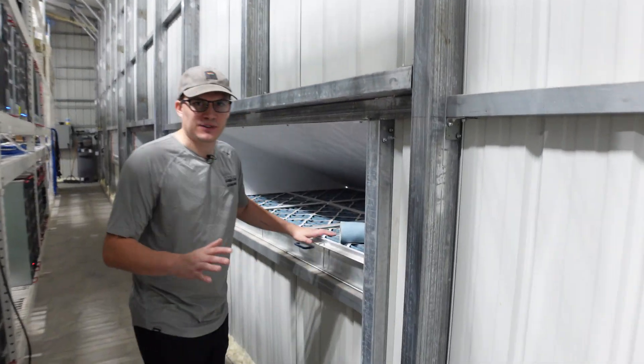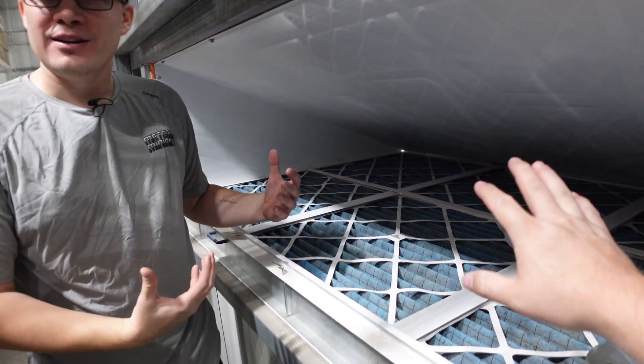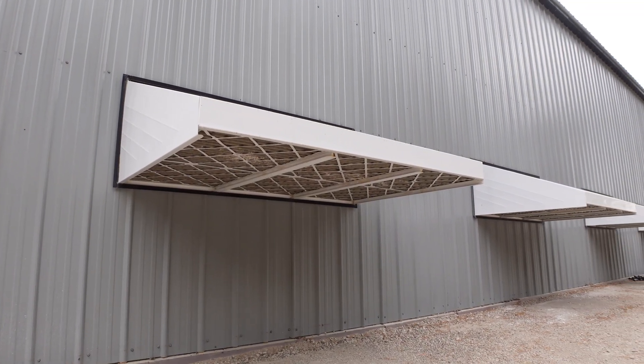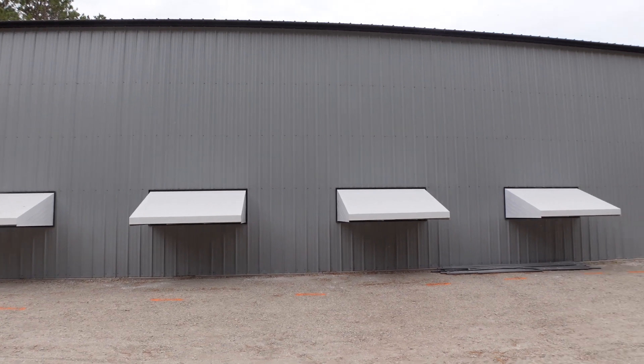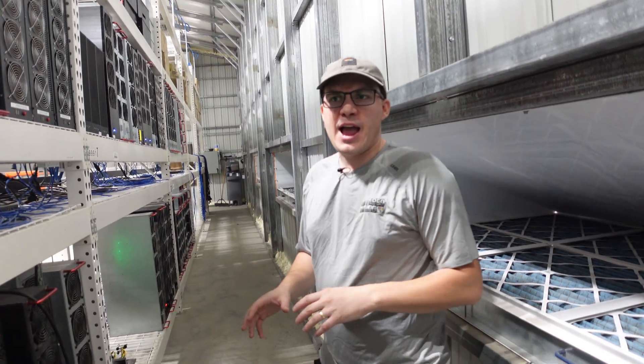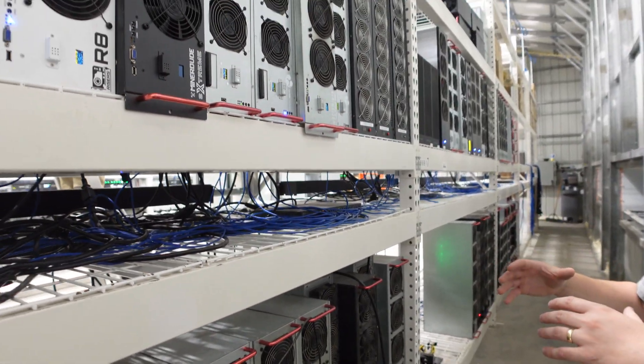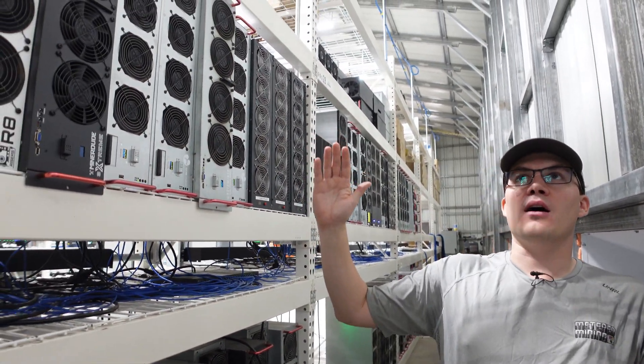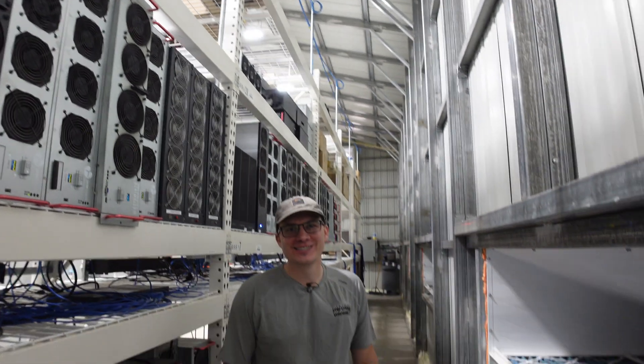Airflow is all passively done. The exhaust fans pull in fresh, cool, filtered air — you can feel it coming in. We're actually doubling the amount of intake, adding eight more awnings to bring in more fresh cool air. In the next couple of months we'll also be blocking off the cold aisle on the sides of the racks. The middle of the building is considered the hot aisle. Fresh air comes in, goes through the equipment into the middle, and then exhaust goes up and out through each end of the building.